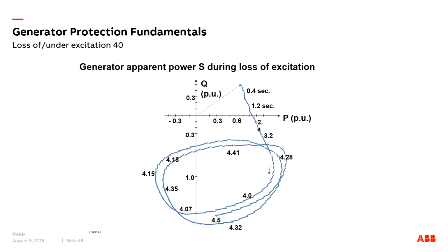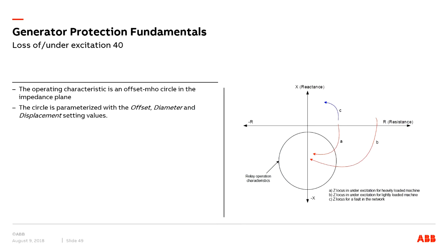So in a loss of excitation condition, the apparent power locus moves in this fashion. We can see that the apparent power takes a path like this. The operation characteristic is typically an offset Mho circle in the impedance plane for loss of excitation detection, and this circle is parameterized with the offset, diameter, and displacement setting values.